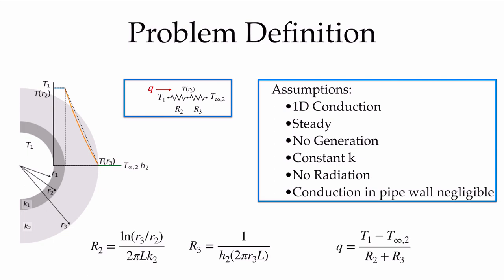Our conduction resistance — this is a cylindrical system where the radius is increasing through the insulation — is the natural log of the outer radius over the inner radius, divided by 2πL times the conductivity of the insulation material. Our convection resistance is 1 over hA, where the area is based on the outer radius R3. Our total heat loss from the system is the temperature difference between the pipe and the ambient over the sum of these two resistances.